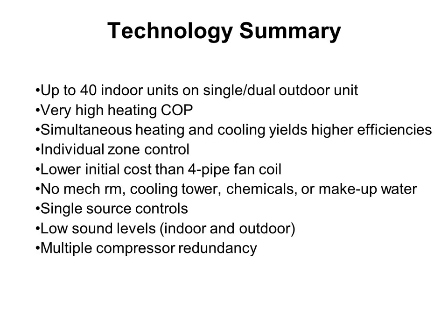One other nice thing about a VRF system, if you're trying to get higher efficiency systems without having to have hydronics involved, you can get rid of the cooling tower and obviously the chemical treatment of the cooling tower and all the makeup water for the tower and the boilers by going with one of these refrigerant-based systems. Additionally, you can also save some floor area because you typically don't have mechanical rooms. You have small zone units that are above the ceiling or on the wall instead of in closets taking up space. You have a single source supplier for your controls. Your equipment manufacturer and supplier is your controls manufacturer and supplier. It's all integrated in one and the same.